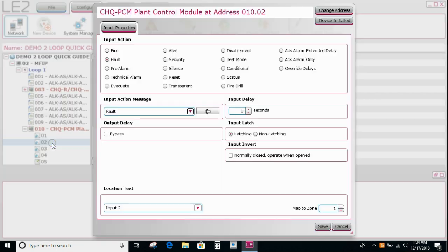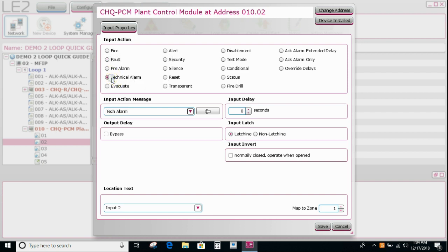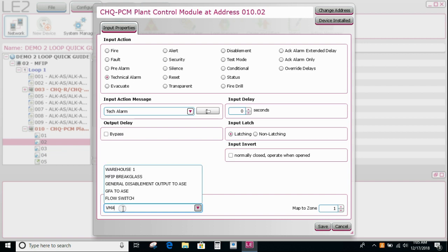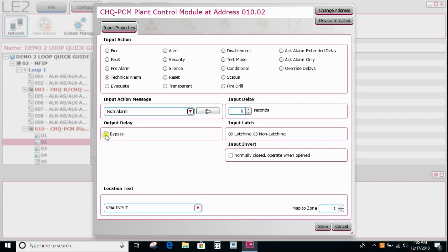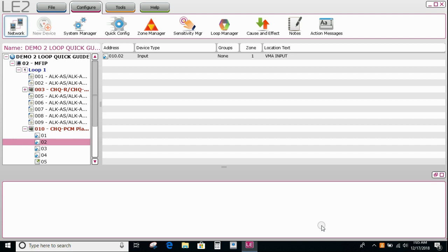And then the second one might be our valve monitor alarm. So the valve monitor alarm, depending on what state you're in, you might require it to be an audible fire event on the panel, or maybe just a fault type event. If it's a fault type event that's going to operate, let's say the ASE input number two, then you can either use one of these others. Typically we can use the technical alarm, and that will come up in the other events tab on the front of the fire panel. So in this case, let's go in and use the tech alarm flag. So I'm just going to put VMA input, and then say save. Obviously we make it latching, bypassing output delays, and then say save.